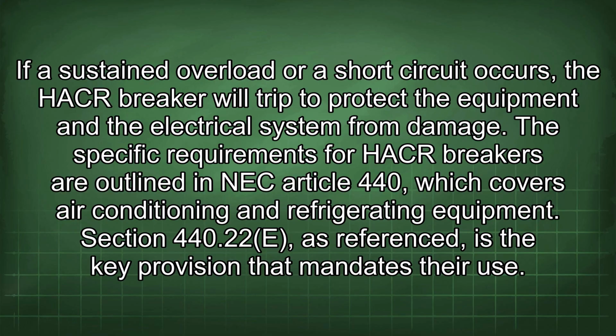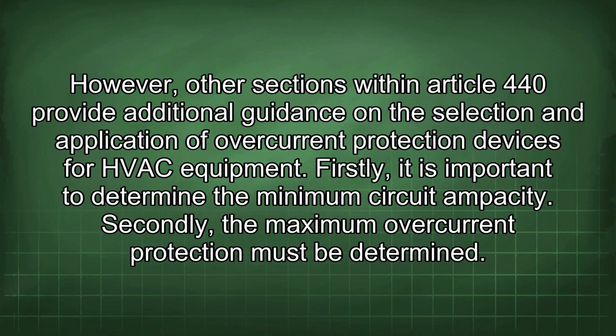The specific requirements for HACR breakers are outlined in NEC Article 440, which covers air conditioning and refrigerating equipment. Section 440.22(E), as referenced, is the key provision that mandates their use. However, other sections within Article 440 provide additional guidance on the selection and application of overcurrent protection devices for HVAC equipment. Firstly, it is important to determine the minimum circuit ampacity. Secondly, the maximum overcurrent protection must be determined.